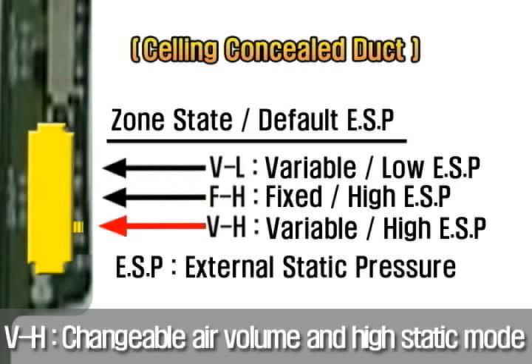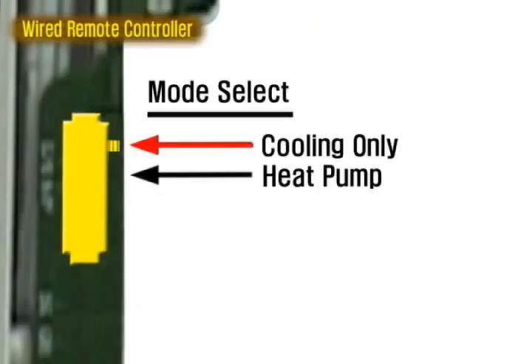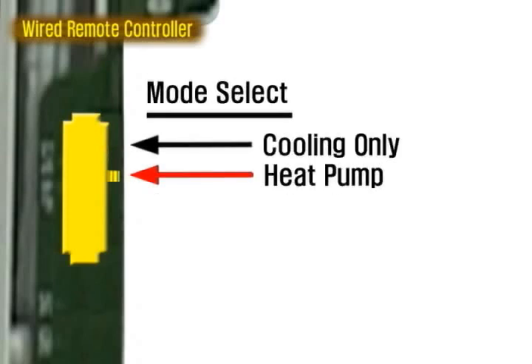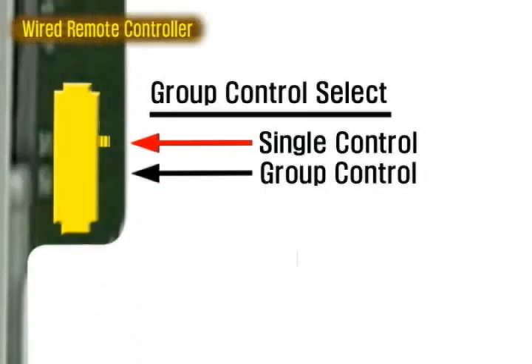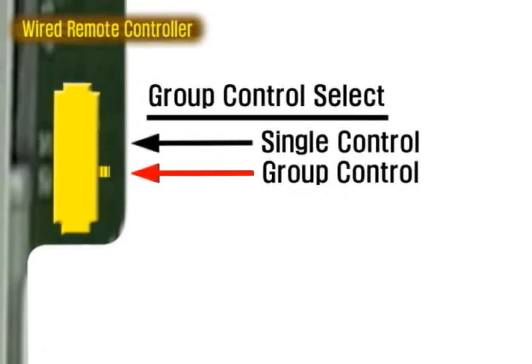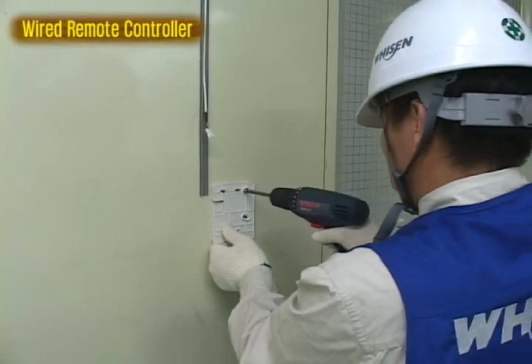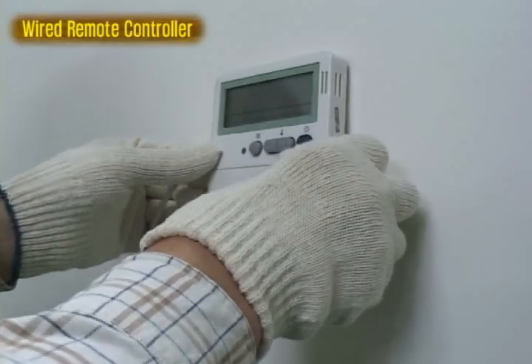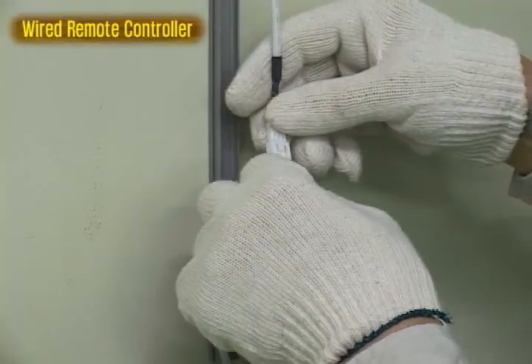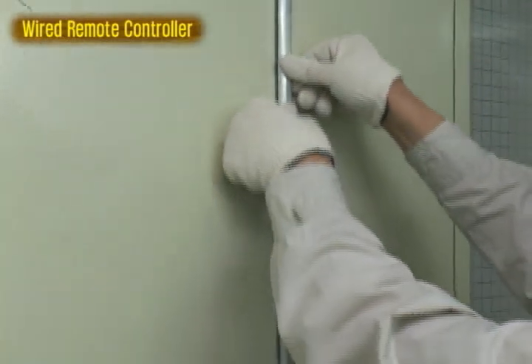V-H is for the changeable air volume and high static mode. If it has a zone controller, fan speed change according to the damper operation. In operation mode select, we have 2 selections, one for cooling only, another one for cooling and heating both. In group control select, single control makes control only for 1 indoor unit and group control for more than 2 with 1 remote controller. Fix the underplate on the wall with screws. Connect the cord to controller, attach the body to the plate, and arrange the protection cover for the cord.